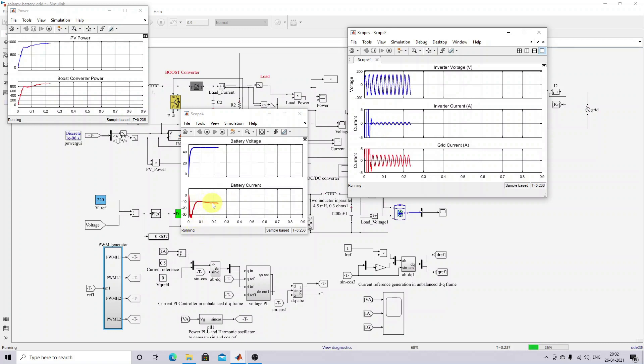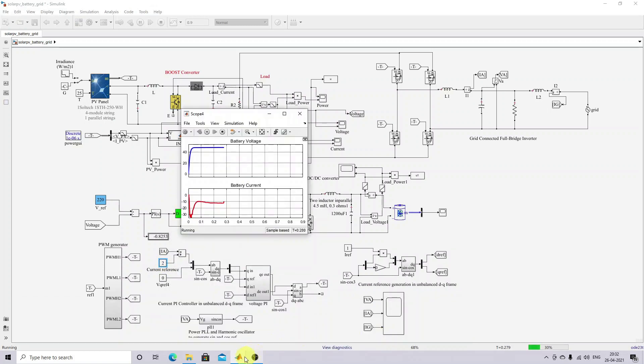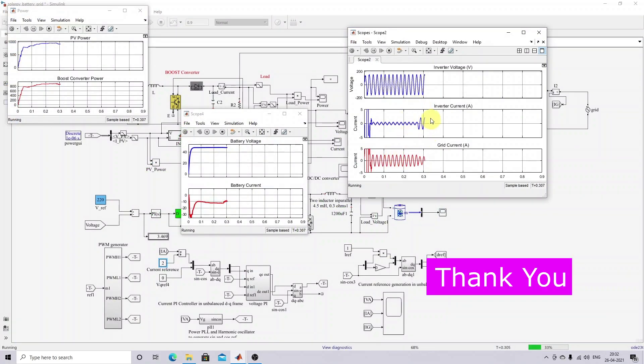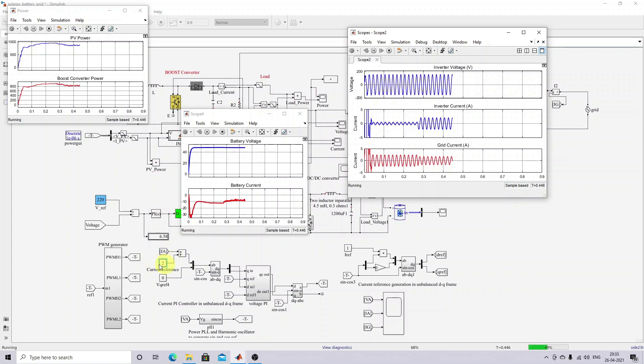Now I'm going to change this value to 2. You will get some changes in the charging of the battery as well as the grid current. The inverter current supplies nearly 2 peak amplitude current because of increasing the current reference from solar PV and battery. You will see a reduction in the grid current sharing, and also the charging current decreases because the solar PV is supplying more power to the grid according to this reference.